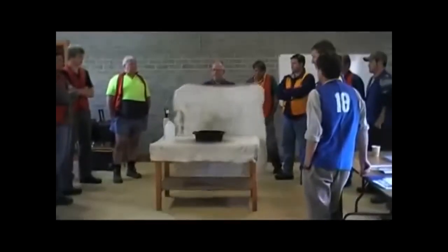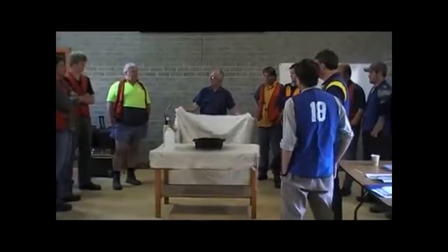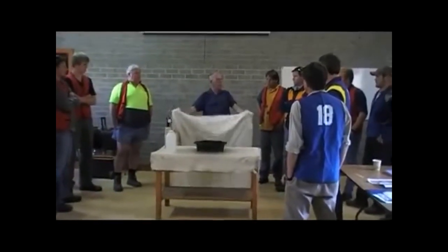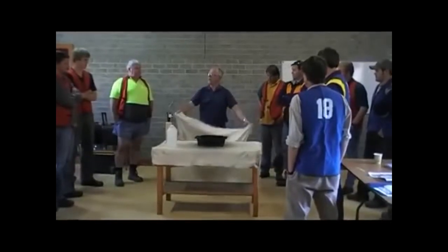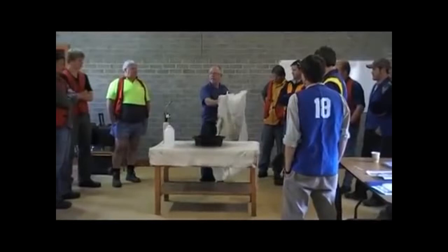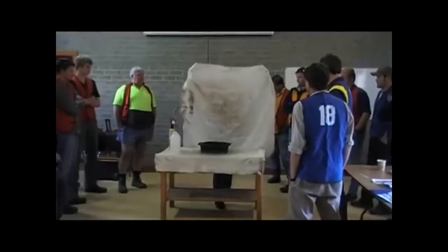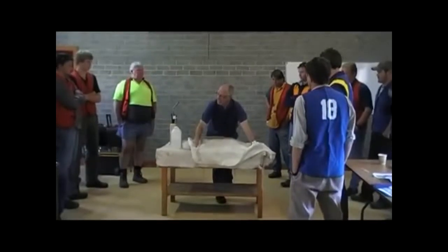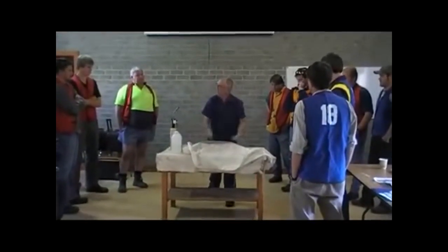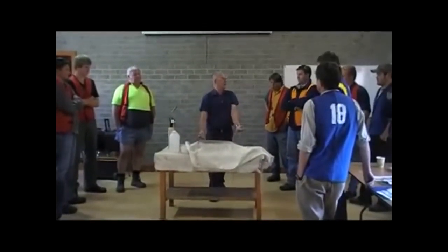Now, because you can get them in different sizes, normally 1.2 by 1.8 metres, when you hold it up, it's normally longer than you, so you can't walk in like that because you'll tread on it. So you need to walk in slowly, sideways, turn and face the fire, arms up high, step forward and put it down like that. What you don't do once you've done that is wrap it around whatever is burning, because then you may pull it back off.